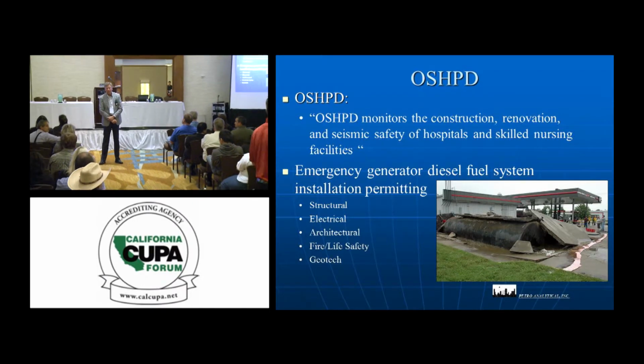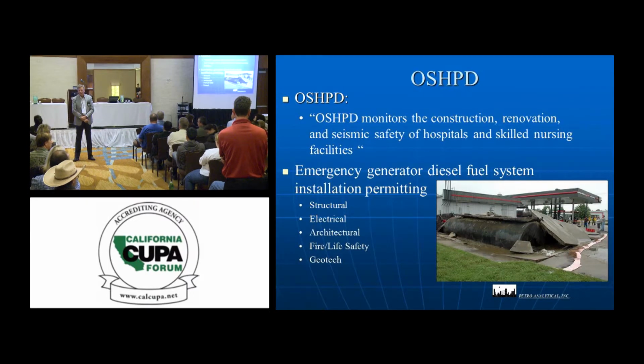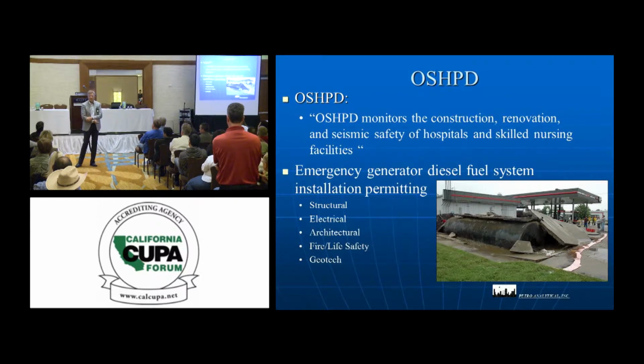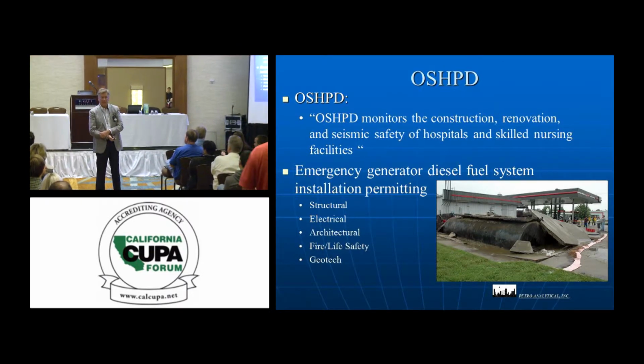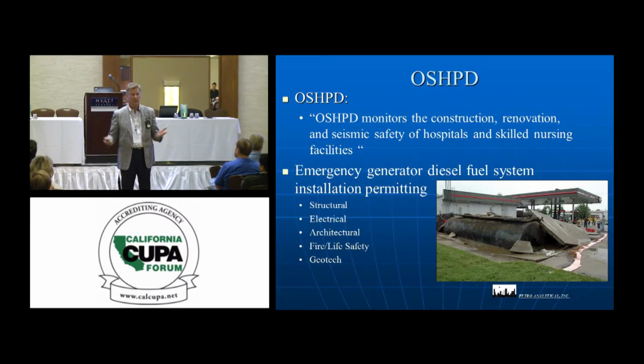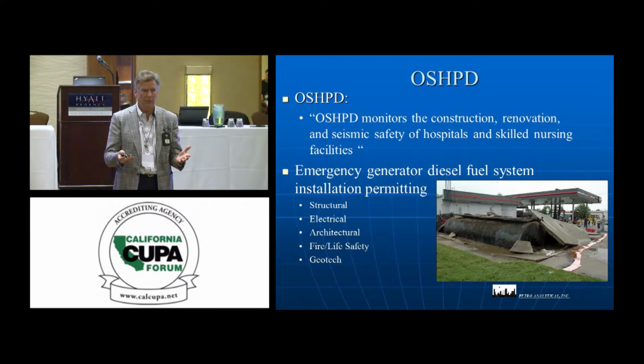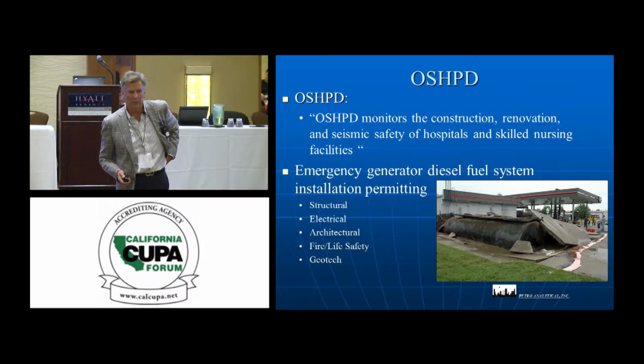Sorry if I missed it, but what is the criteria or the main reason why some generator tanks are vacuum versus pressure? What's the deal? Why some tanks are vacuum versus pressure systems on generator tanks. The tanks themselves? Yeah. Steel tank won't handle hydrostatic. So if you got a steel tank, you automatically default to vacuum. But if we have a fiberglass tank, we don't see any reason to go vacuum there. Is that maybe what you're referring to?